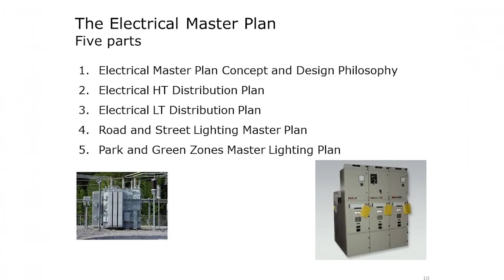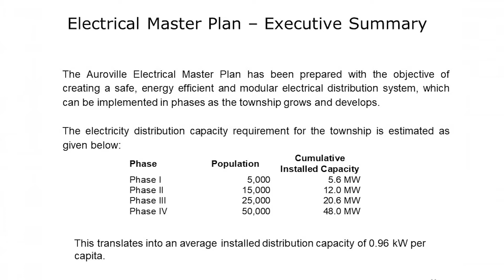They prepared a plan with us, covering all the way up to 50,000 people, but designed so it can be implemented in small steps. It has an HT plan, an LT plan, a road and street lighting plan, and phasing taken from the master plan of Auroville: 5, 15, 25, and 50. It comes to basically a distribution capacity of almost 1 kilowatt per person.